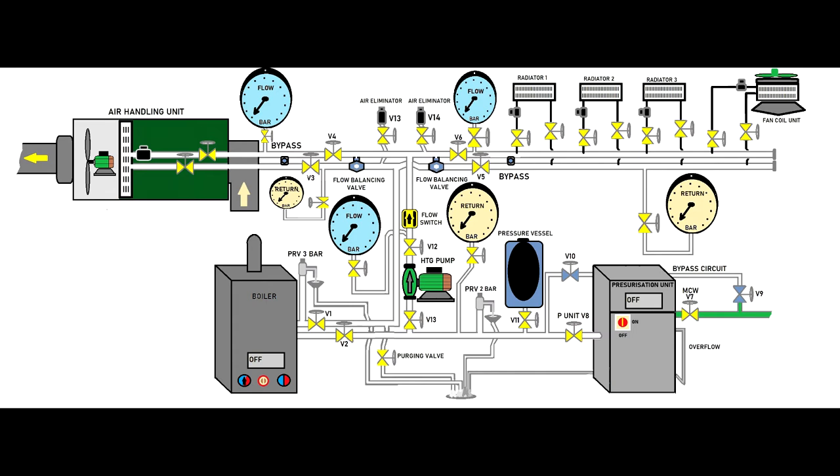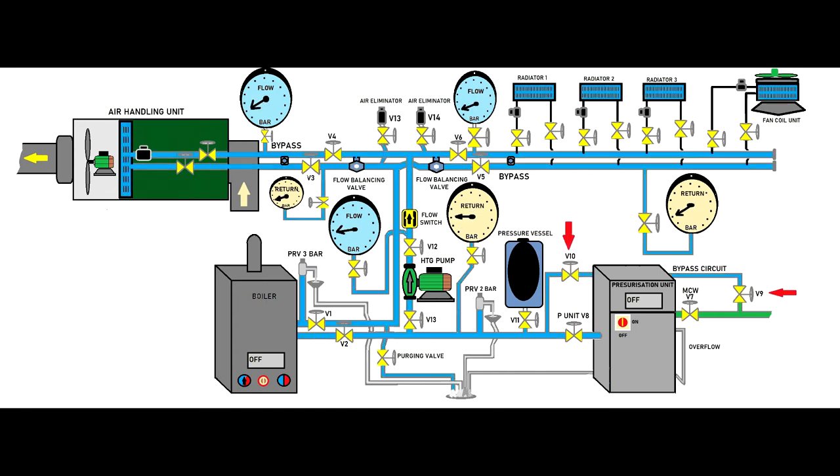I have an answer for that too. I don't use the pumps excessively, and while I'm filling the installation, I think using the main cold water system and the pressure available onto the system is okay for the first filling. I have another very thorough visual inspection, and then I will fill normally the system with water. So I will open the bypass, both valves, allowing the water to go from the main directly into the system. And when I open the purge valve, then the water will close the circuit.